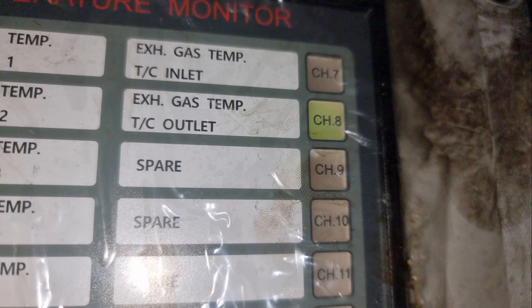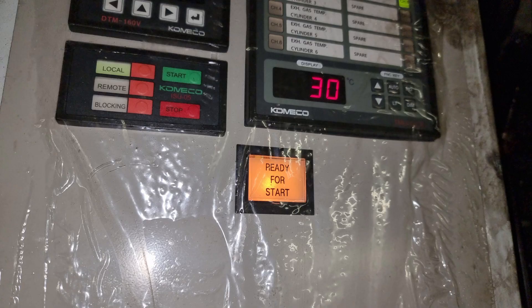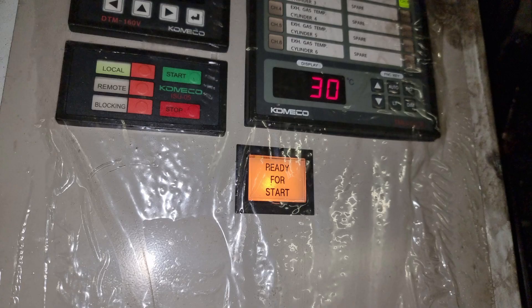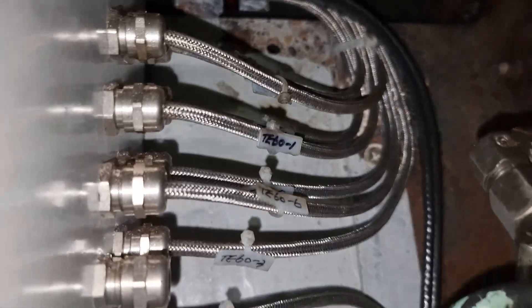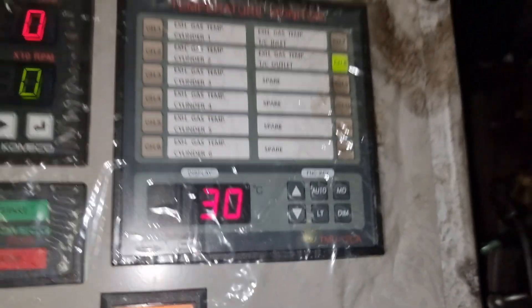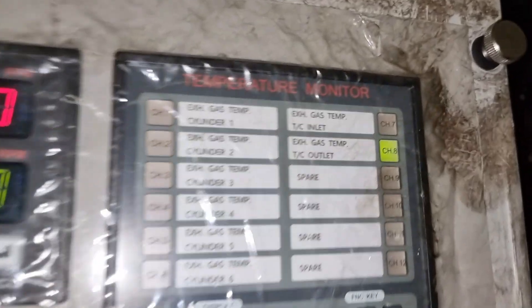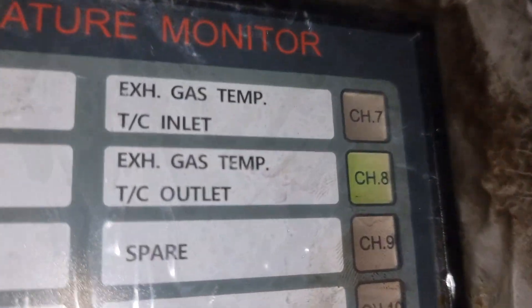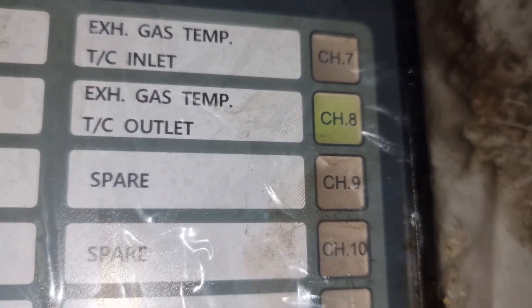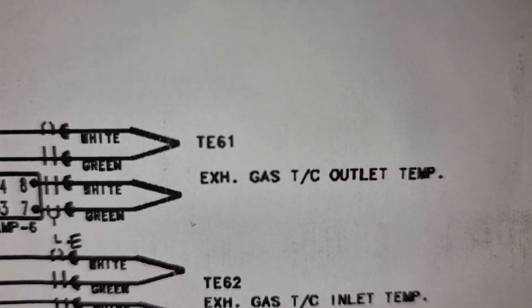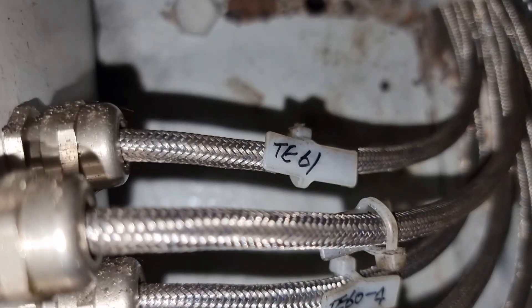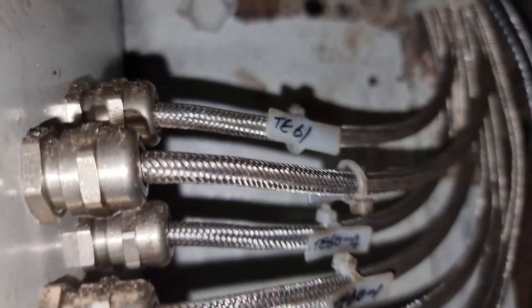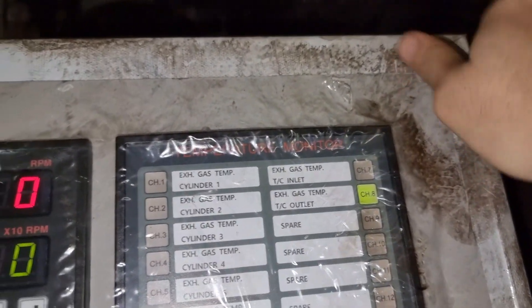The sensors have two pairs of wires. One pair is for the local display and the other one is for the alarm and monitoring system. For the local display, it is working fine except for the alarm and monitoring system. As per manual, the sensor name is TE61, which is this cable TE61. So let us now check the connections inside.